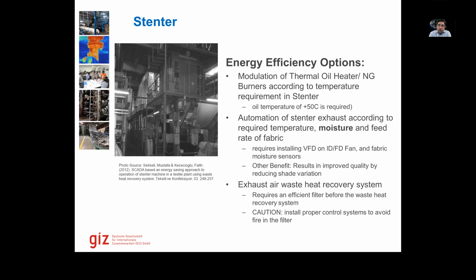A usual recommendation is that we should heat up the oil only up to a level where, when the oil returns, it has at least dissipated 8 to 9 degrees Celsius of heat. That can be achieved if we have an oil heater running at 200 degrees Celsius. Oil goes into the stenter, heats up the stenter to 150 Celsius, and returns at around 190 to 193 degrees Celsius. That is when we can optimize the thermal oil as well.